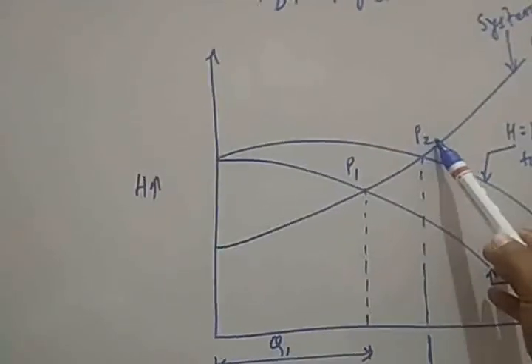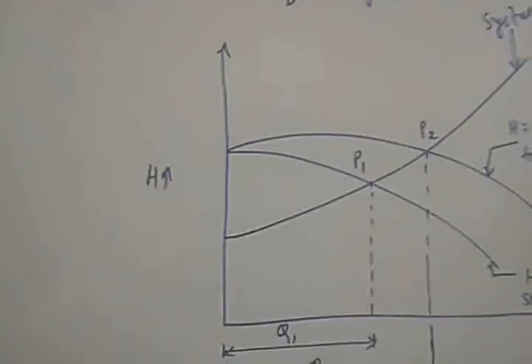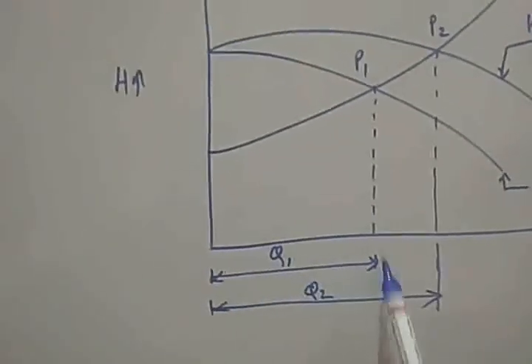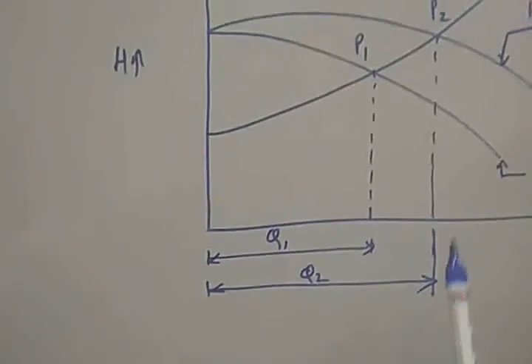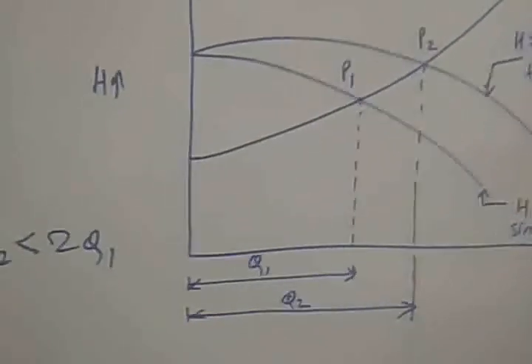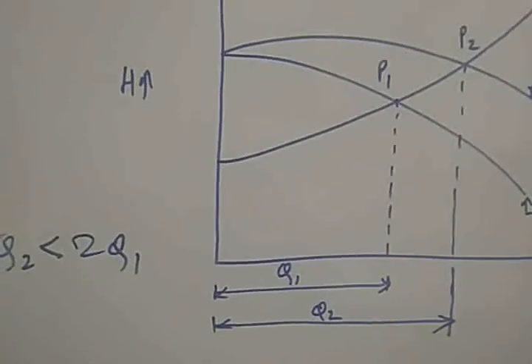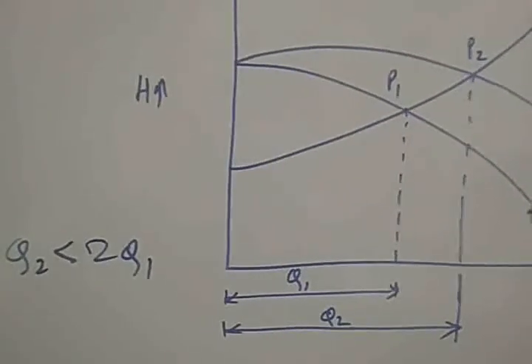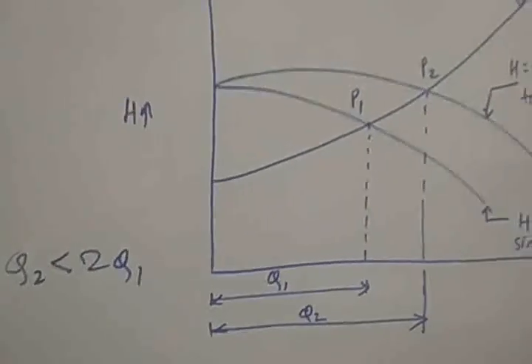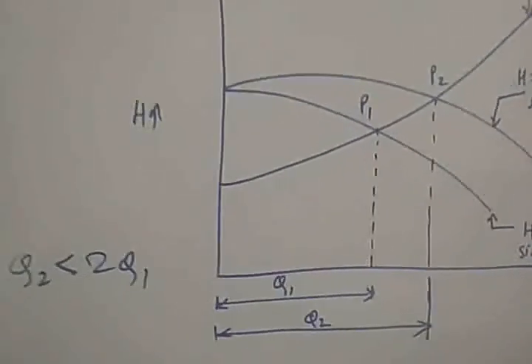The point of intersection for two pumps is higher than for a single pump. Accordingly, Q1 corresponds to the single pump and Q2 to the two pumps. We can see Q2 is less than 2Q1 — so as with series, using two pumps in parallel does not give double the discharge. We will be selecting a proper pumping unit according to the requirement of the discharge. Thank you.